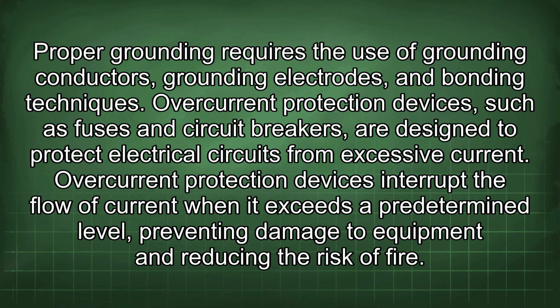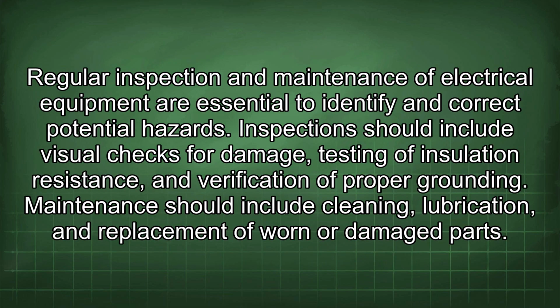Overcurrent protection devices, such as fuses and circuit breakers, are designed to protect electrical circuits from excessive current. Overcurrent protection devices interrupt the flow of current when it exceeds a predetermined level, preventing damage to equipment and reducing the risk of fire. Regular inspection and maintenance of electrical equipment are essential to identify and correct potential hazards. Inspection should include visual checks for damage, testing of insulation resistance, and verification of proper grounding. Maintenance should include cleaning, lubrication, and replacement of worn or damaged parts.